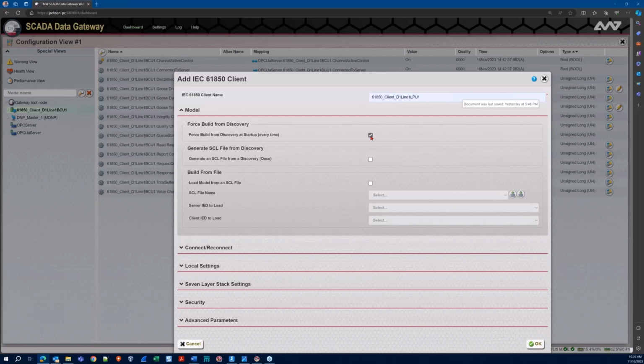So what we could do, if we have our device, our IED, this D1 line 1 LPU available, is fill in the communication settings, connect to it, and discover the data model on that device. But if I want more of a top-down engineering process, and I already have the file defined for this device, I can instead do build from file.